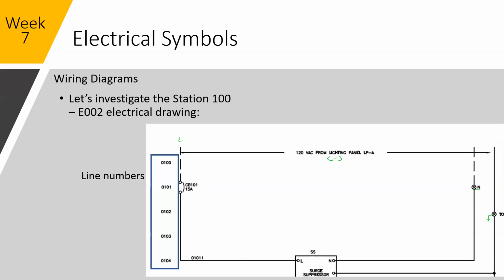So if you're familiar with architectural or mechanical drawings, you'll see inside a lot of drawing title blocks, you'll actually have an A, B, C, and 1, 2, 3 grid going up the side and down the side of the drawings. For electrical drawings, what you're typically going to see are line numbers. These will be broken down into, or should be. Not every company follows drawing standards, but there should be a correlation between 01 and your drawing number and your line on those pages.